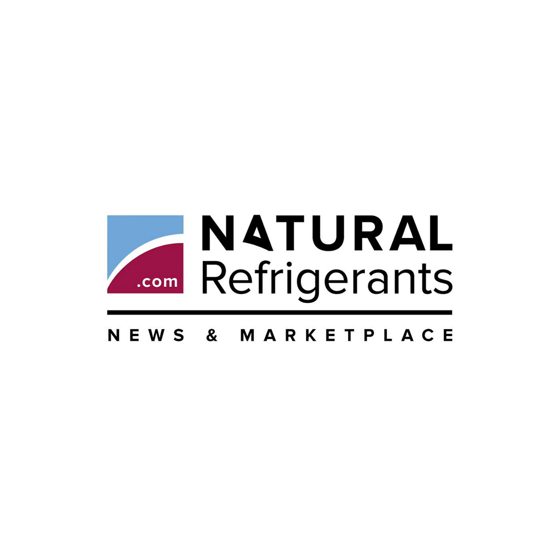Other SCM Frigo news: the manufacturer continues to invest in large-scale CO2 equipment with two recent installations, one in France and one in Ecuador. The company delivered a 1.5 megawatt (426.5 tons refrigeration) plug-and-play CO2 transcritical rack system, providing 6 degrees Celsius (42.8 degrees Fahrenheit) cooling to a cosmetics and pharmaceutical company. The system includes 1 megawatt (284 tons of refrigeration) of heat recovery for space heating and hot water production.